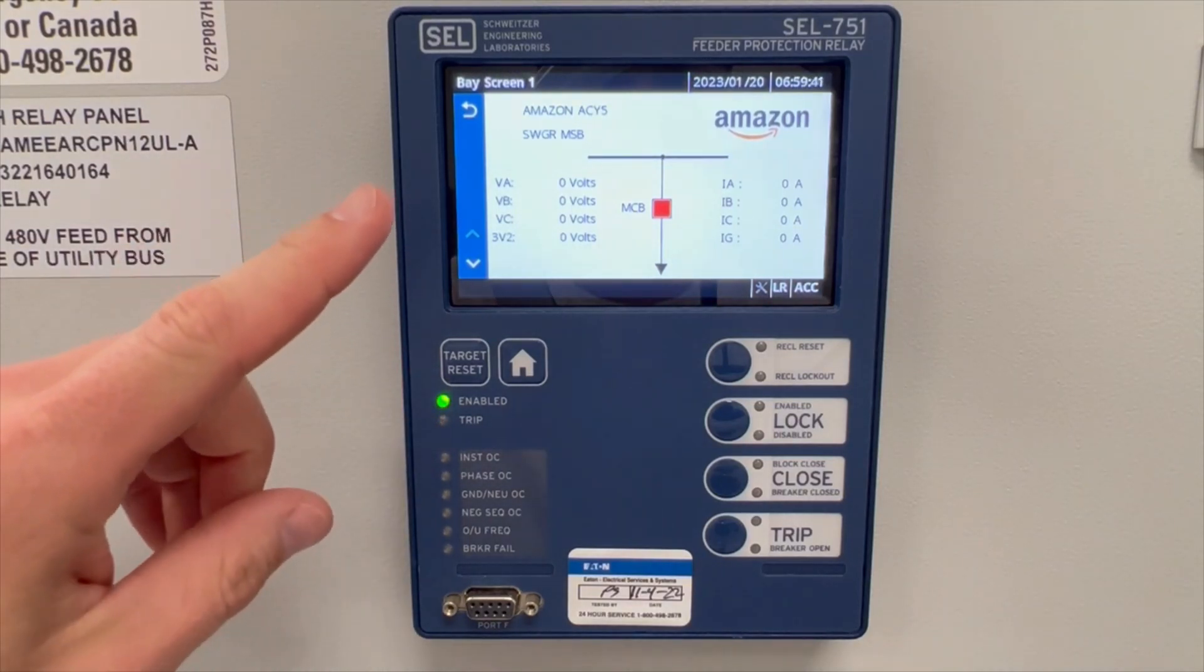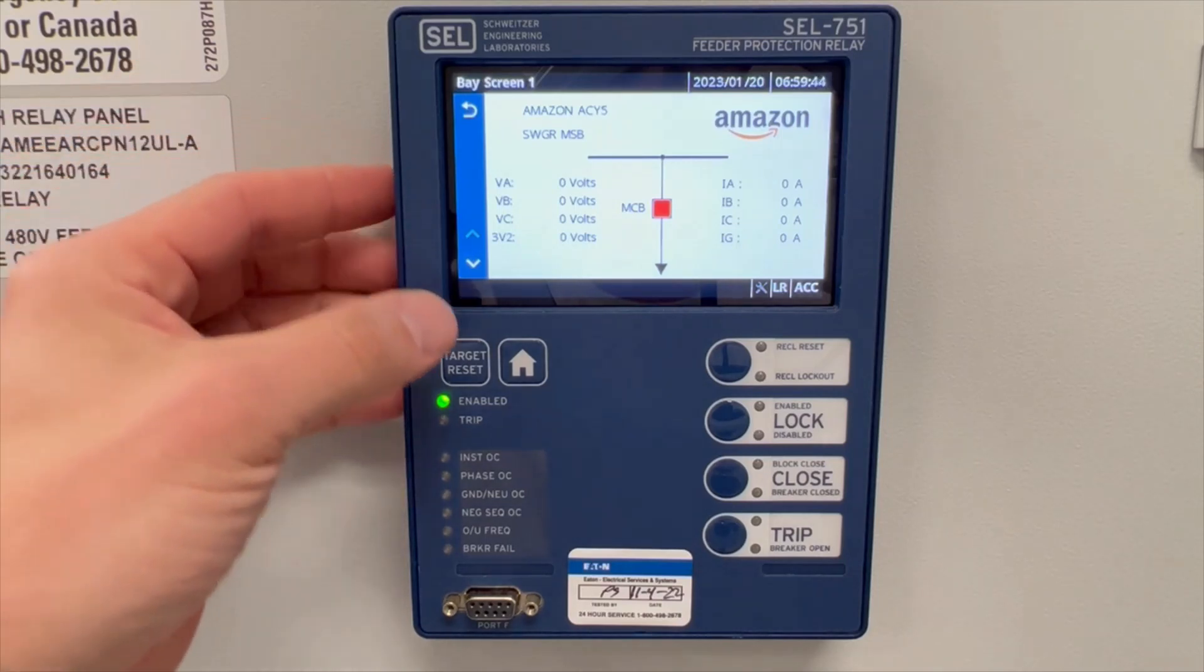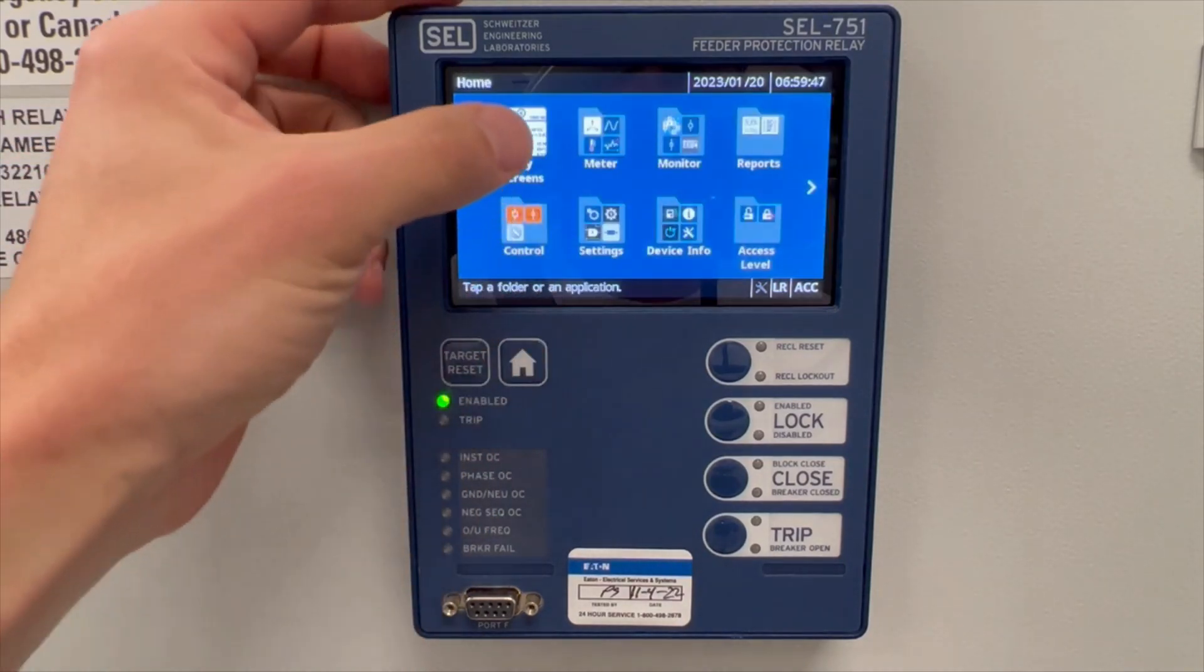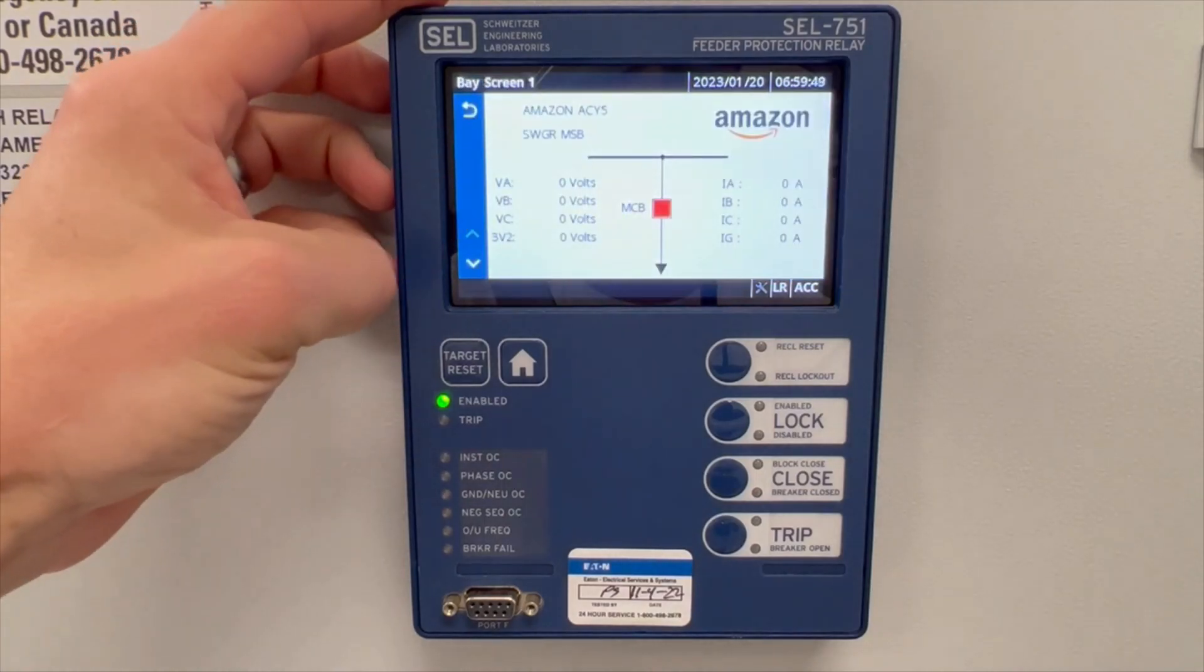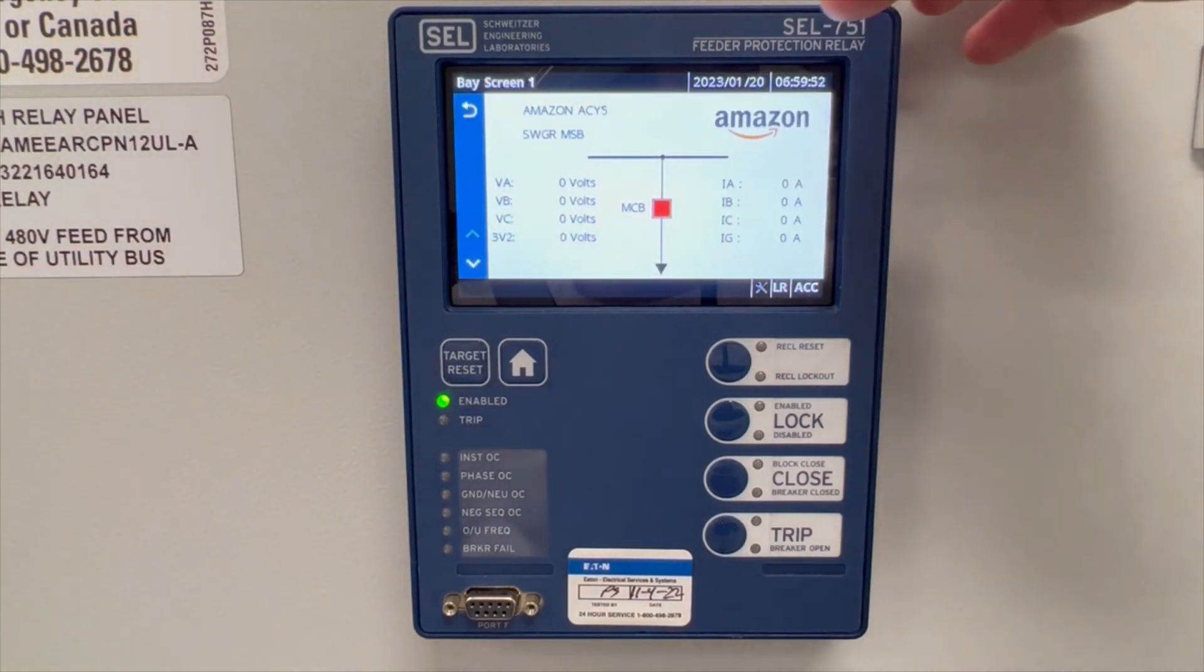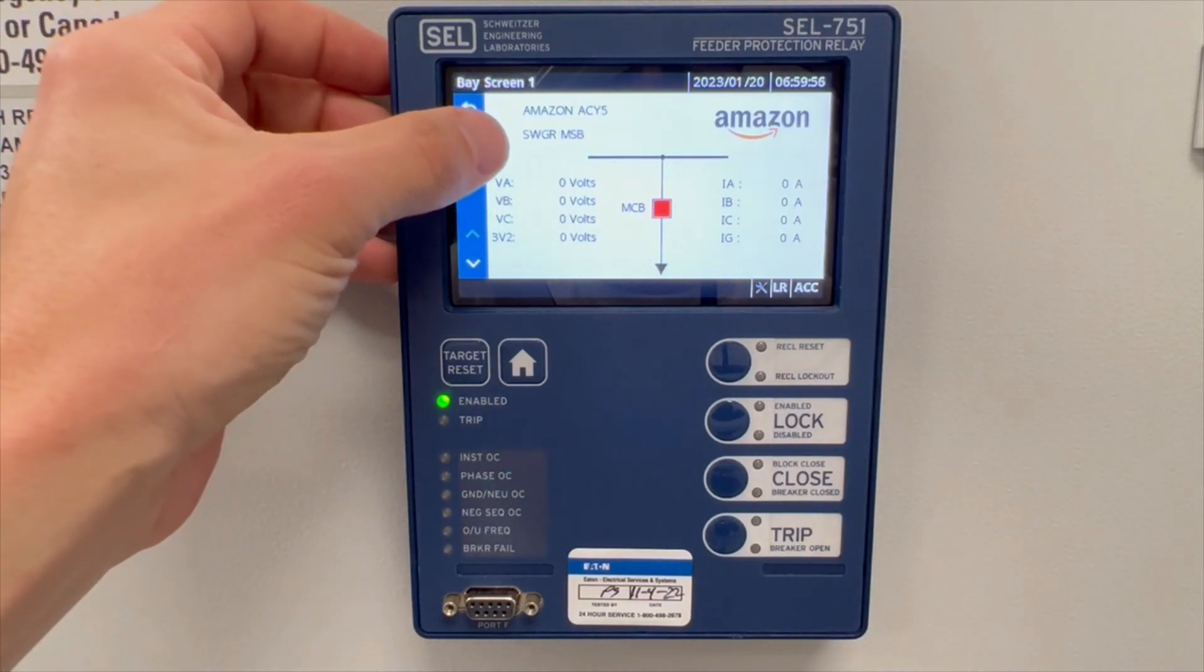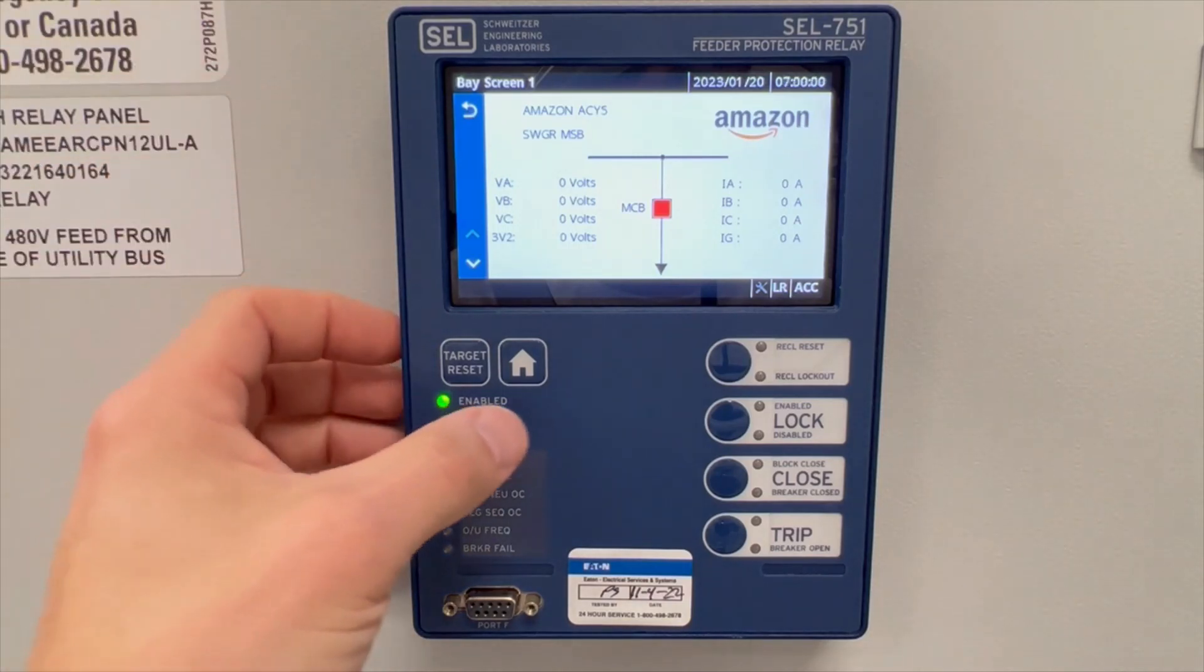The base screen is the screen that the relay will typically default to. If it's not in the base screen you can hit the home button and touch the base screen icon. Once you're in the base screen, verify that the time and date are correct. Also verify that the site and the switchgear ID are correct. If any of these are incorrect, make a note of it.